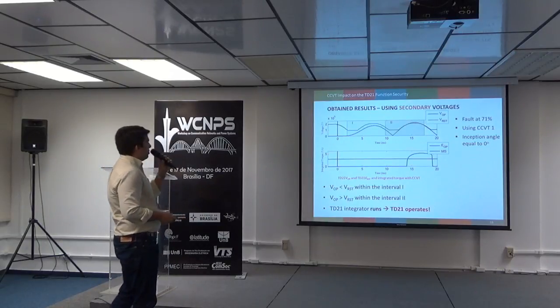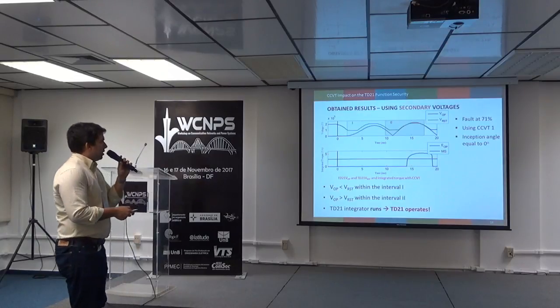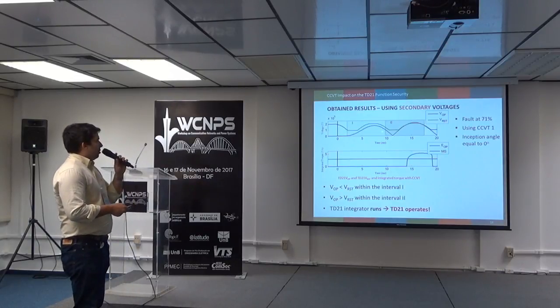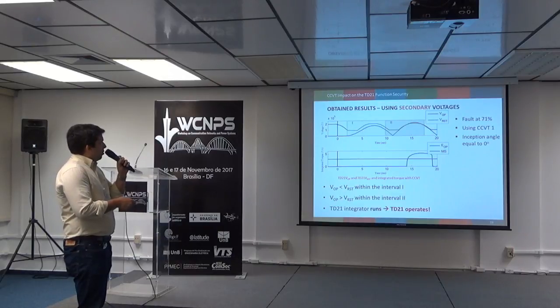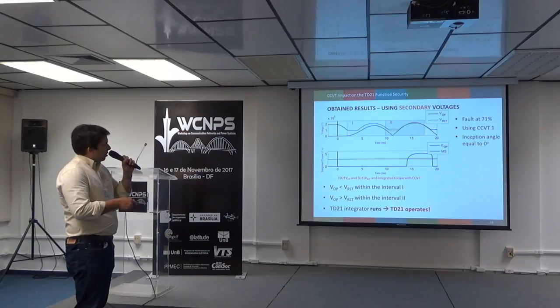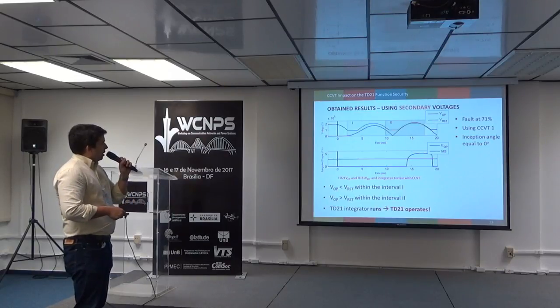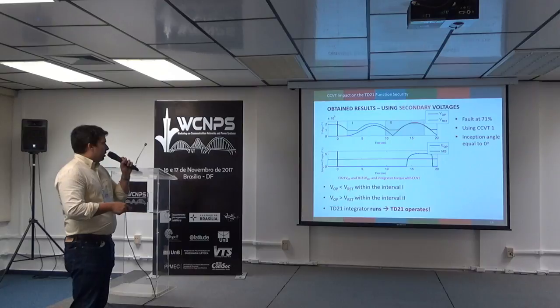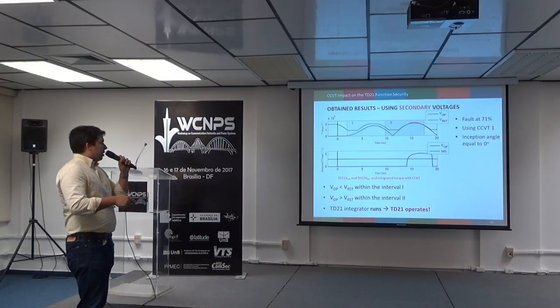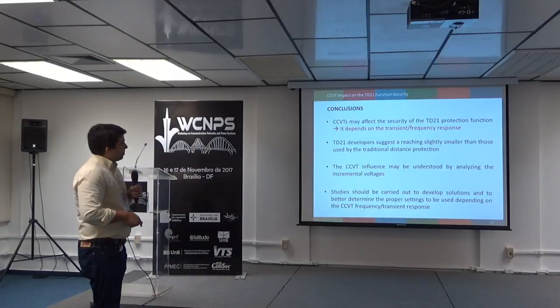On the other hand, when we use secondary voltage for the same case, we can see that at the first stage of the signal, the operating voltage does not exceed the restraining one, but within the second stage here, the operating voltage exceeds the restraining voltage, so the integrator runs, and then since the integrated signal exceeds the threshold, the TD21 operates.